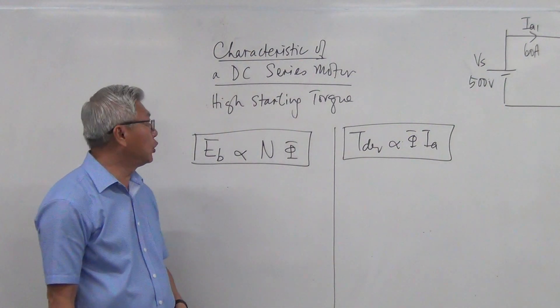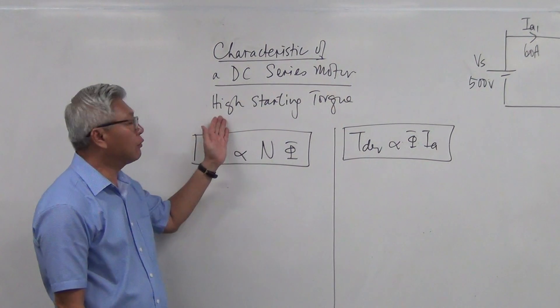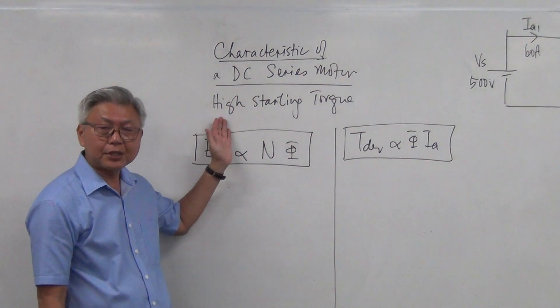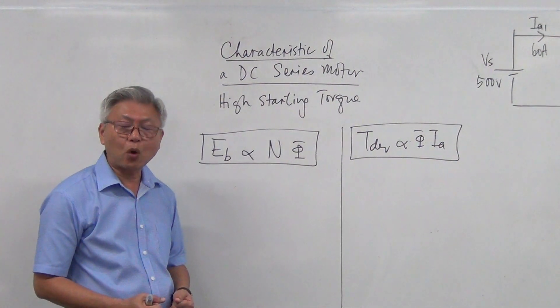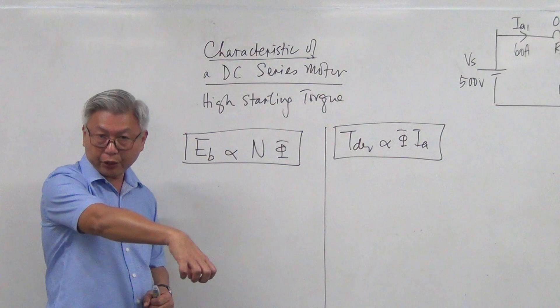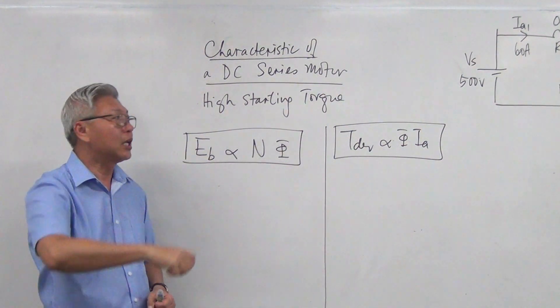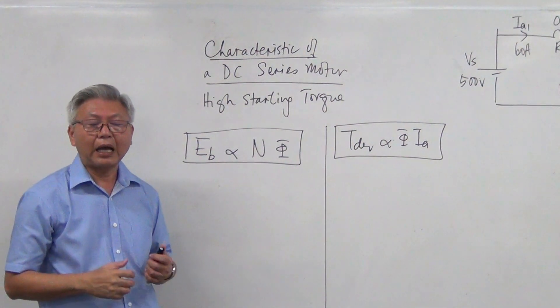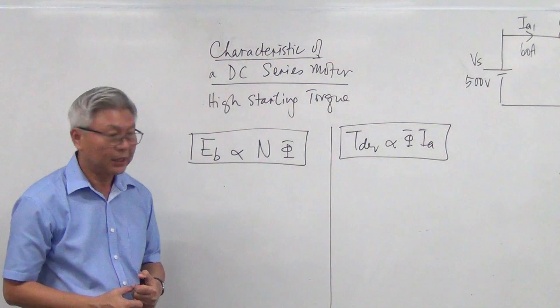Welcome back. We will now continue with the characteristics of a DC series motor. Now DC series motor's main characteristic is that it has high starting torque, and because it has high starting torque, it's very suitable for applications such as cranes where you need to lift up heavy objects at the beginning and then it will slow down. Things like this, high starting torque, DC series motor is very suitable.